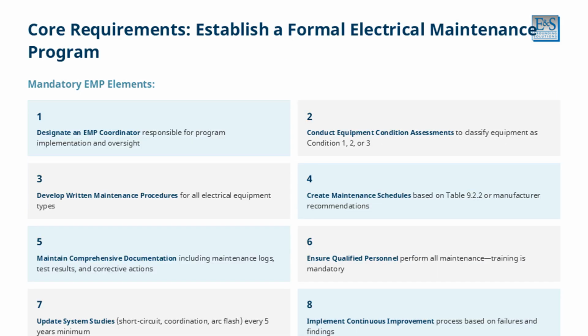Every facility must establish a formal electrical maintenance program with 8 mandatory elements. First, designate an EMP coordinator responsible for program implementation and oversight. Second, conduct equipment condition assessments to classify equipment as condition 1, 2, or 3. Third, develop written maintenance procedures for all electrical equipment types. Fourth, create maintenance schedules based on Table 9.2.2 or manufacturer recommendations.